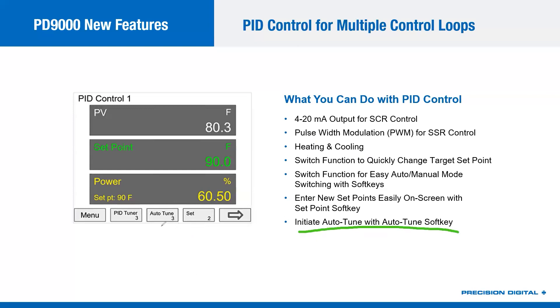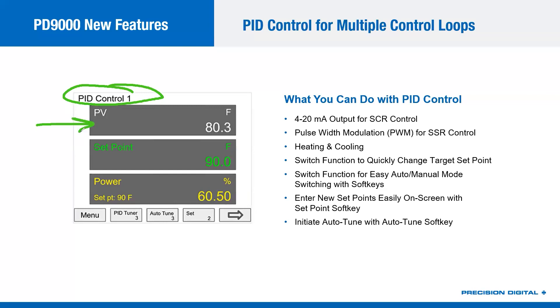You can create a dedicated PID control screen showing the process variable, set point, and the power percentage on the outputs needed to drive the PV to the set point. For example, you can see we're driving that 80-degree process variable up to 90 degrees, putting 60.5% on the output. That output could be a 4 to 20 milliamp going to a power controller, or a relay turning on a heating element — lots of different things that output could be.